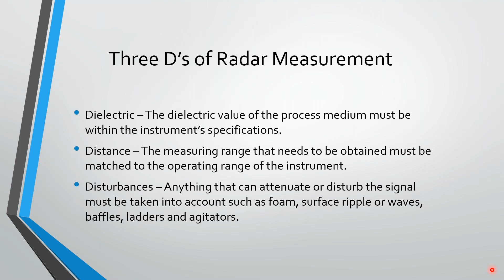So the 3 Ds of radar measurement: dielectric, right? We want to make sure the process medium is within the instrument specifications as far as dielectric value. Distance: we want to make sure that we pick the proper instrument for the range that we're trying to measure, because there are instruments available for different ranges. Disturbances: anything that can attenuate or disturb the signal must be taken into account. Foam, surface ripple or waves, baffles, ladders, agitators, anything else within that vessel can cause reflections that we don't want and contribute to noise.